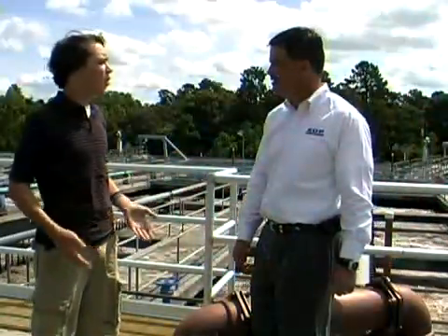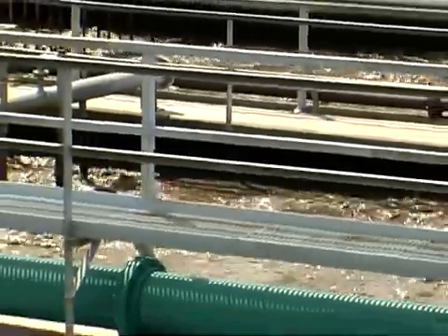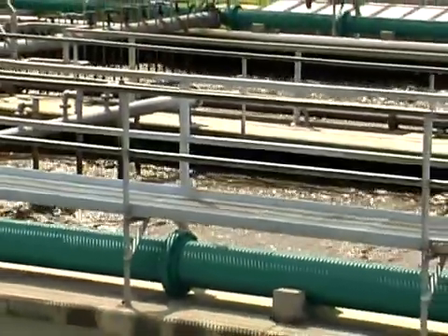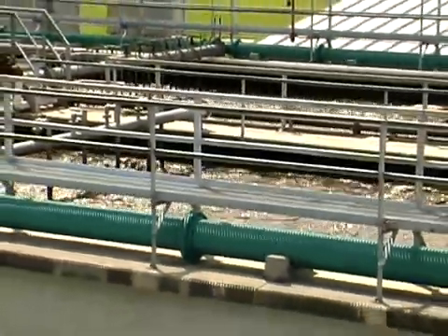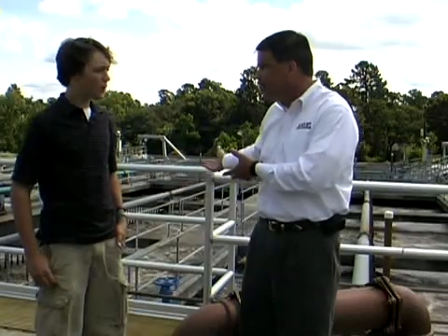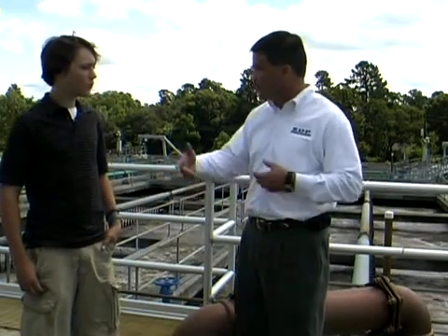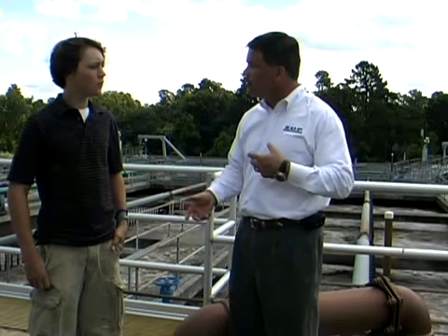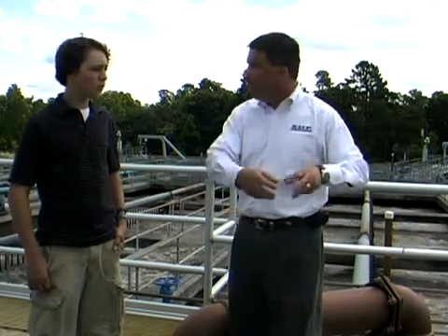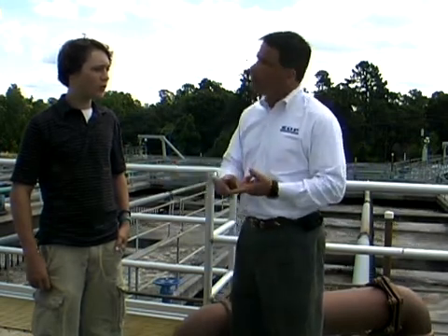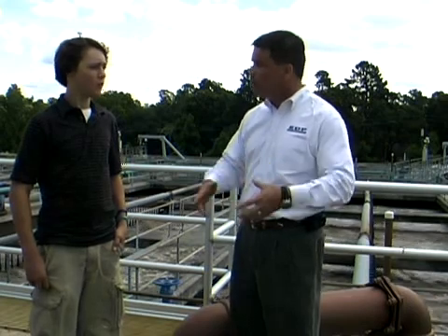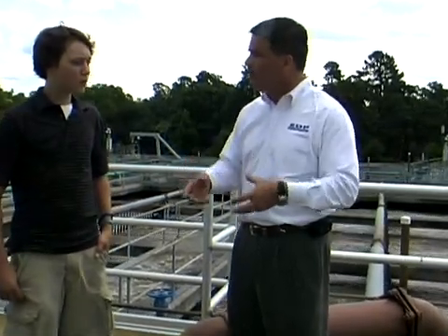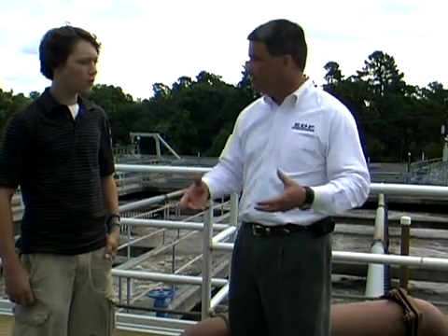Why does that one look so much darker than this one? The digesters over here are much darker. The solids that we have in there, the bacteria, the biosolids that we grow, we concentrate into that tank. Now we don't add a food source or an energy source like we do with the process up here. Here they're getting the raw organic material from the waste stream. Over there we don't give them any more food. So a lot of them die off and are converted to CO2 and water. Then the remaining part that's left over when they die off is consumed by the other bacteria as their energy source. So not only are we concentrating the bacteria, we're reducing the total amount of dissolved solids and the total amount of settleable solids in the wastewater.